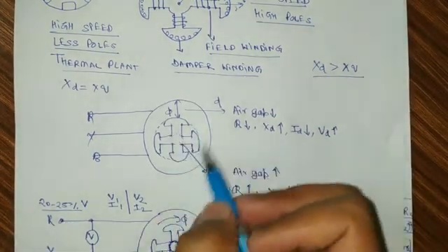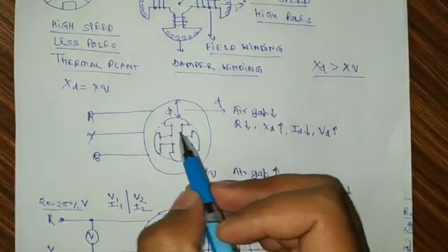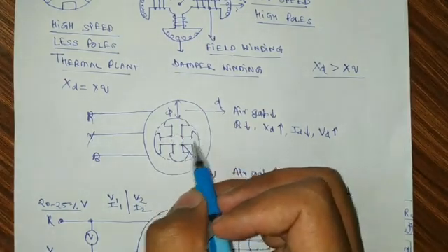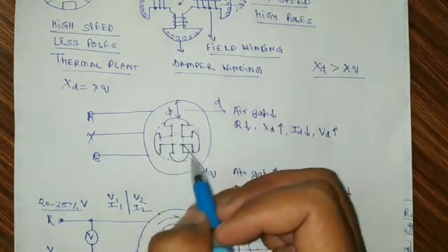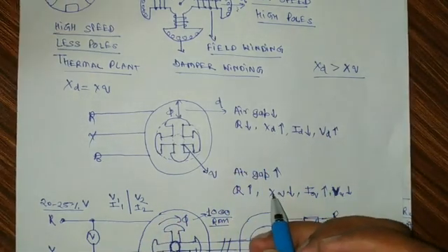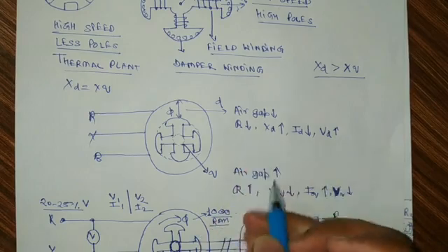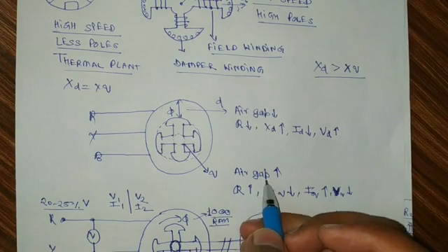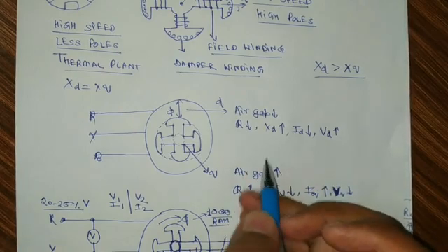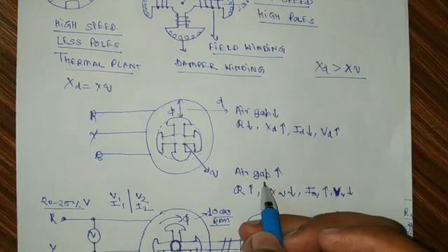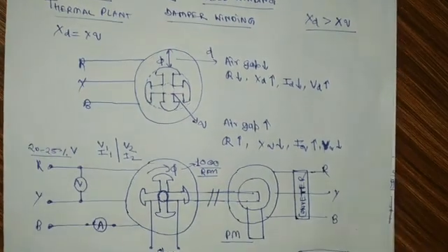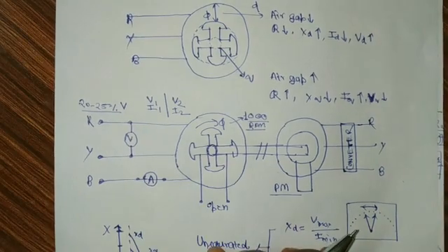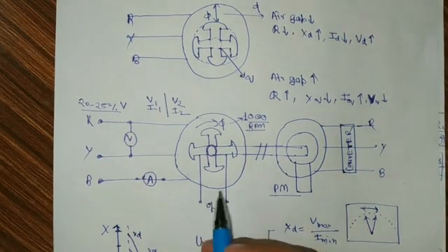This type of rotor put in a stator can be assumed as having one small rotor and one outer big rotor. Both will have different reactances, which we call Xd and Xq. Now how do we find Xd and Xq? Whenever we are doing some test on any synchronous machine, we need to find these parameters to calculate efficiency, voltage regulation, and many other things. This is the testing arrangement for the slip test of a salient pole synchronous machine.